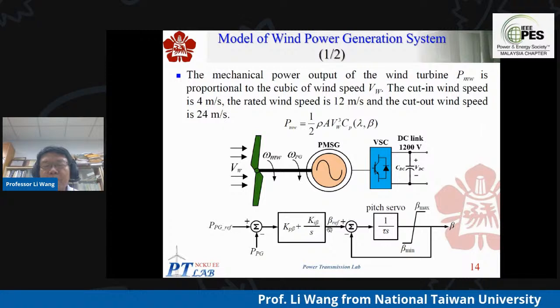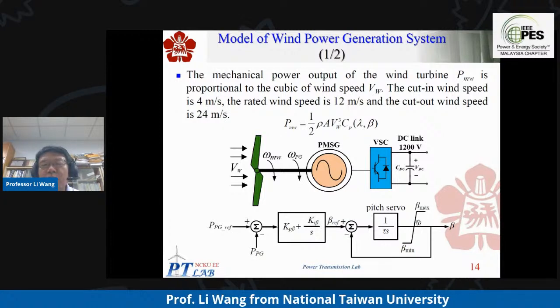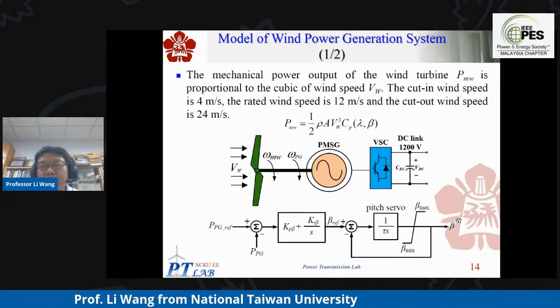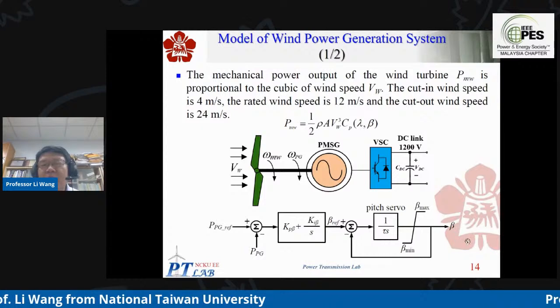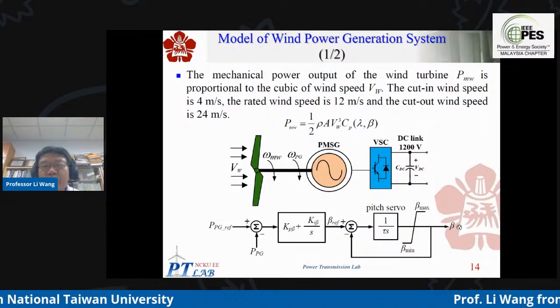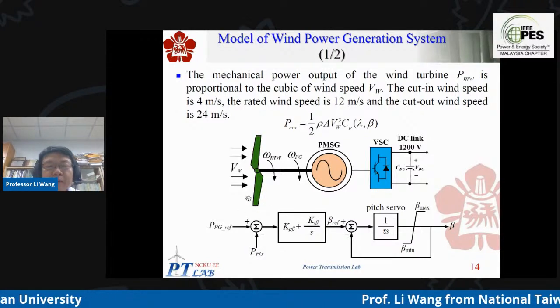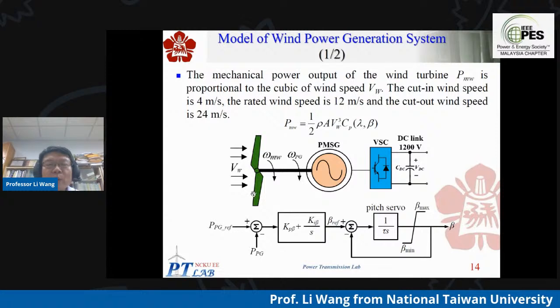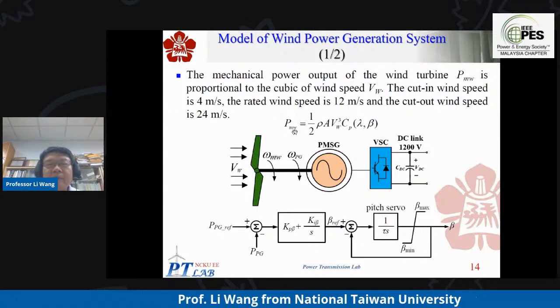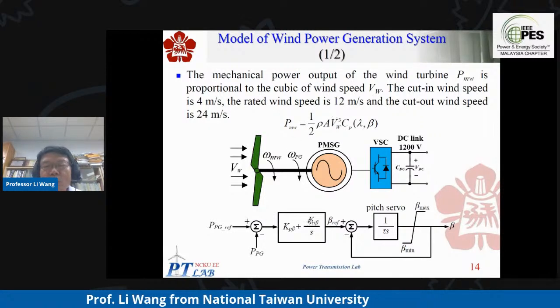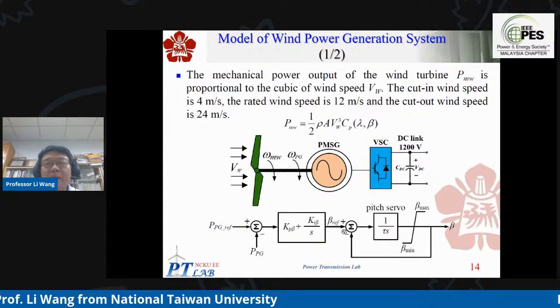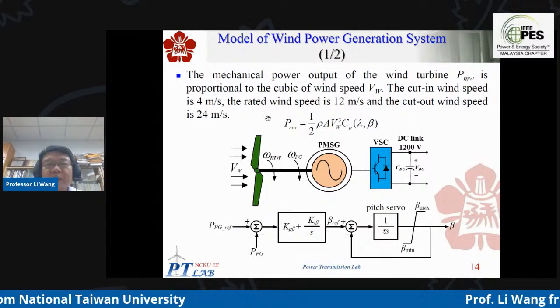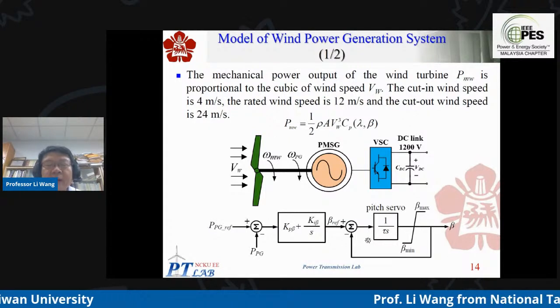Then the pitch angle goes through the pitch servo, so we can get the actual pitch angle of the pitch angle control system. This pitch angle controls the blade angle here. So when the wind speed is too high, higher than the rated wind speed, this one will be activated. But if the wind speed is lower than the rated wind speed, then this control block diagram cannot operate.